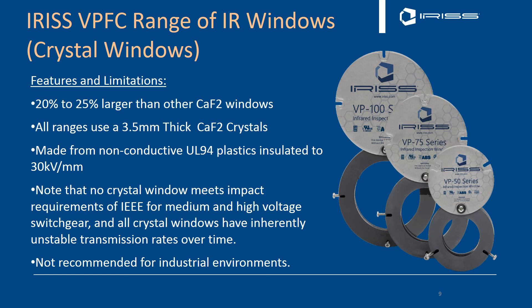Let's look at the types of infrared window available from Iris. The first is the VPFC crystal range. Our windows are 20–25% larger than most other calcium fluoride windows in the marketplace. Our viewing diameters are true viewing diameters — if we say a four-inch window, it has an actual four-inch viewing diameter. You may see windows in the field called four-inch where the actual viewing diameter is only 3.5 inches. All our windows have the same crystal thickness of 3.5mm across the whole range, so you're not adjusting for different transmission rates due to different thicknesses. Our window housings are made from non-conductive UL94 plastics, insulated to 30,000 volts per millimeter — a nylon-6 based plastic, the same type used for making contactors in switchgear.